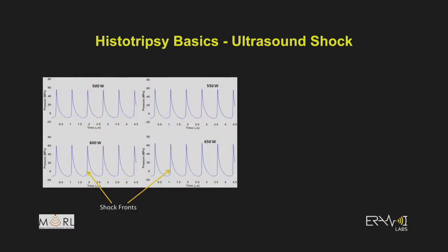So I think these waveforms may be obvious to some people who are doing shockwave lithotripsy. These are basically ultrasound shocks that you produce when you increase the amount of acoustic power. So electric power converts to acoustic power, which converts to acoustic pressure, and it's this pressure that you use for imaging, and that determines how the image quality looks. Now, obviously, on your diagnostic imaging device, you can't change that, because it's FDA approved. If it's FDA approved and labeled as such, you can never touch the power. You can reduce the power, but the maximum power is possibly what you're all using.